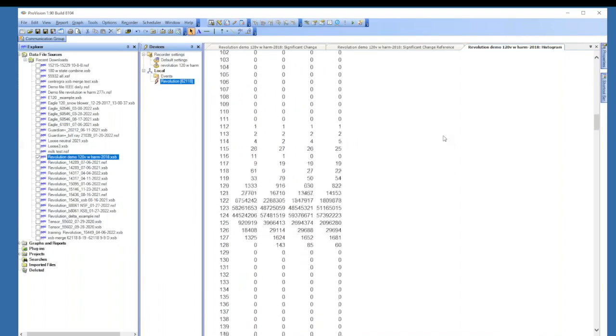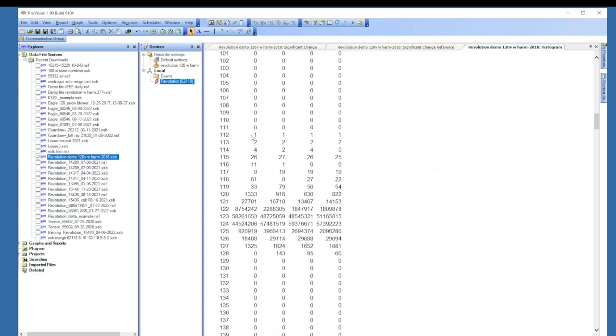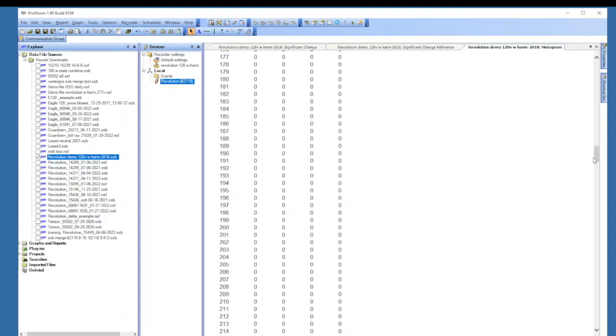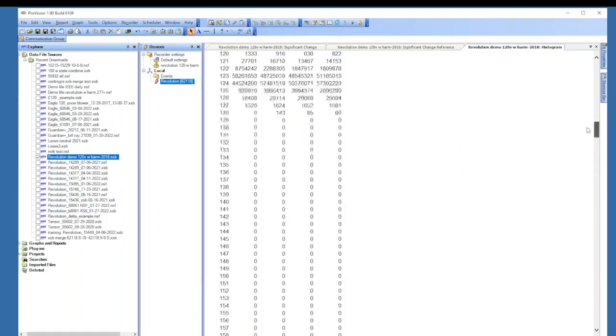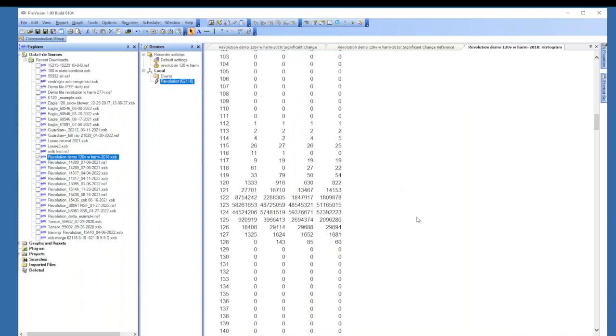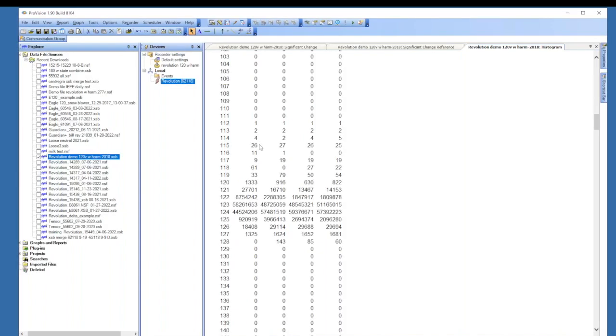So as we slide down here, we can see that we had one cycle at 112 for channels. This is channel 1, channel 2, 3, and 4. Don't know why we have that voltage on 4, but we do. But you can see, and it does go down all the way to 599. So you can see every cycle that was recorded and where that voltage came in at. So we had 26 cycles at 115. So if they're complaining about flicker, then you would see a lot of cycles down here.